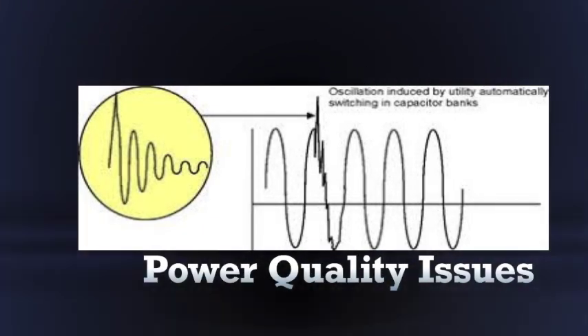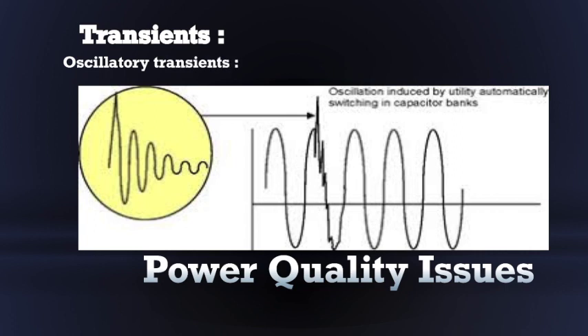Now you can see a figure. In this figure you can see oscillatory transients which are bipolar in nature. This has occurred due to switching in of capacitor banks. Now the question is how we are going to mitigate transients. The equipment can be protected from the transients by removing sources of potential ESD and using surge suppression devices. Good wiring practices can also help in reducing the effect of transients. High frequency filters can also be used to suppress oscillatory transients.